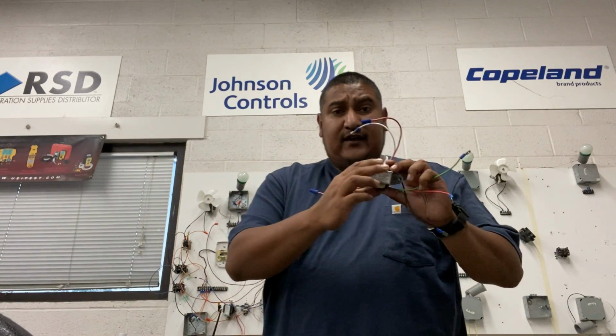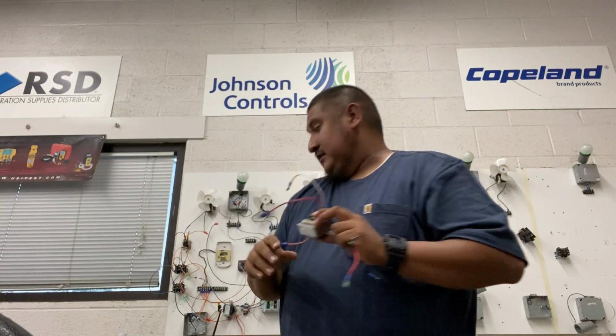Now, what I always tell my students is to think of a heavy load machine. The one I always use is an excavator. You know what an excavator is. It's the one with the big arm that digs a bunch of holes. Who does the job, the excavator or the operator? It's the excavator. The excavator is doing all the digging, all the work. But what's telling that machine how to perform the work? It's the operator. So if we take that scenario, the big machine is the high voltage, 208 volts, 240, 480 volts. That's the one doing the big work. And then the operator, the guy who's actually driving the machine, is the control voltage. That's basically what's going on right here. This is why we need this transformer. It's going to drop it down to 24 volts, and that's going to be doing all the main controls.